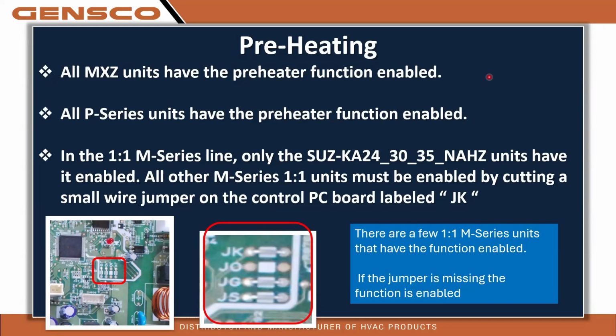And if that JK is there, as shown here, it's a small wire jumper. Take a small snip and snip that. Bend it out of the way so it can't make contact, and the crankcase heater will be enabled. You now have to have power on without the unit running for a minimum of 12 hours.